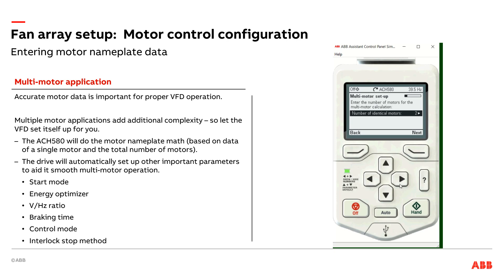I'm going to enter into the drive how many motors I have for this application. I'll just say it's a small two-fan array, so simple two motors here. But I could hit the right arrow and change this all the way up to 18 motors. Technically the drive could run more than 18 motors, but at some point application-wise, does it make sense for a single drive to run all 18 motors? Or should we go with one drive per row, one drive per column, or a checkerboard approach to that fan array? So we limited it to 18 for this particular functionality.